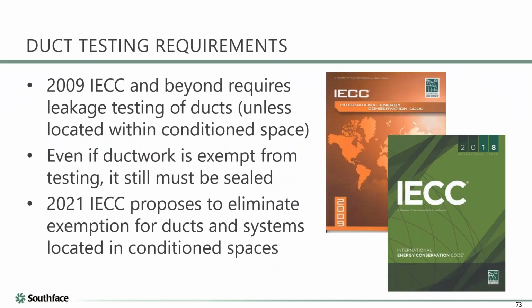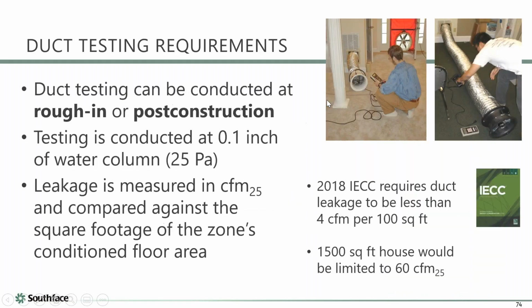So the codes have required duct testing since 2009. It was pretty easy in the 09 code. It was 12% leakage, and it would allow you to not have to test if you have the ducts inside the envelope. And it looks like they're considering getting rid of that in the future code. It's in there as a carrot right now. You can test ducts by the newest code today.